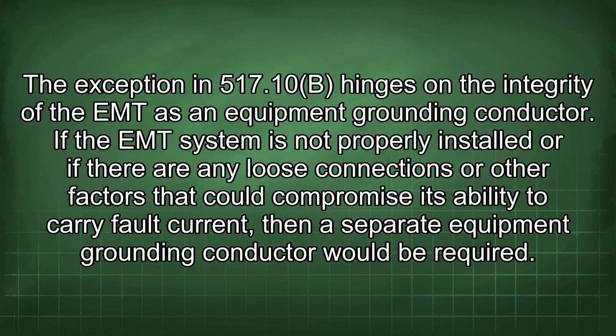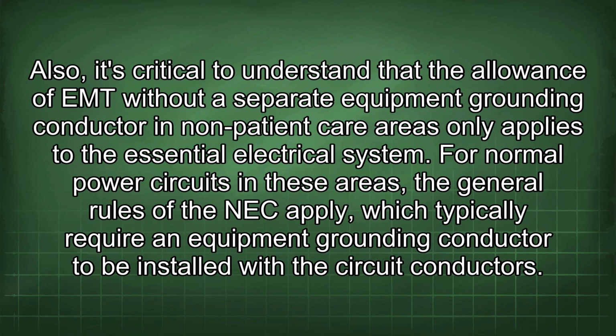The exception in 517.10(B) hinges on the integrity of the EMT as an equipment grounding conductor. If the EMT system is not properly installed, or if there are any loose connections or other factors that could compromise its ability to carry fault current, then a separate equipment grounding conductor would be required. Also, it's critical to understand that the allowance of EMT without a separate equipment grounding conductor in non-patient care areas only applies to the essential electrical system. For normal power circuits in these areas, the general rules of the NEC apply, which typically require an equipment grounding conductor to be installed with the circuit conductors.